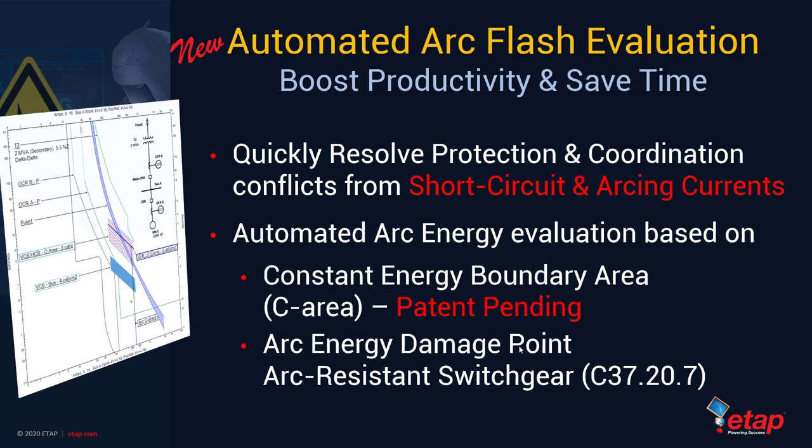Majority of the time is spent collecting settings for protection and coordination, but thereafter it's the balancing act between the bolted fault current and the arcing current. We are always trying to find an optimal setting for protected devices that meets coordination adequacy and safety through bolted fault current and offers personnel safety against arc energy release in case of an Arc Flash event. Automated Arc Flash evaluation allows you to balance and arrive at an optimal setting between these two varying fault currents using a concept of constant energy boundary area, or C-area.